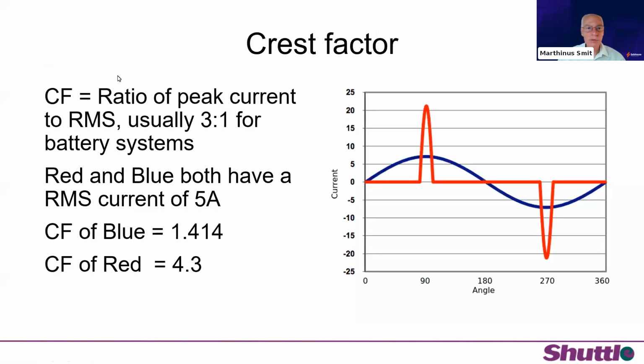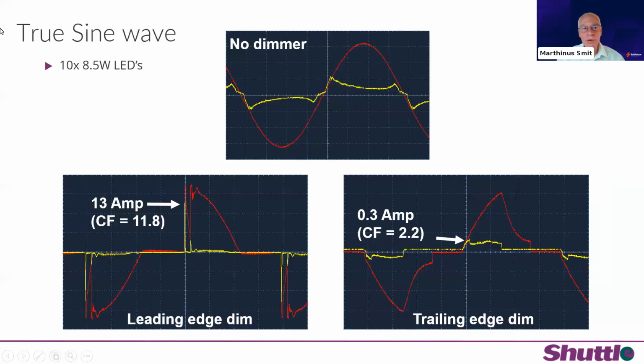So I'm not going to spend much time on the current crest factor. That just says what the ratio is between your peak current and your RMS current. But most of your inverters are designed for a crest factor of 3 to 1. Now, if we look at the case of the 8.5 watt LEDs on a true sine wave, the yellow is the waveform if you have no dimmer installed. And then if you have a leading edge dimmer installed, you can see that your crest factor goes up to 11.8, which means immediately you're far exceeding the ratio of 3 to 1 for your inverter. And you can see that the measured current waveform shows a 13 amp current peak, which your inverter has to supply.